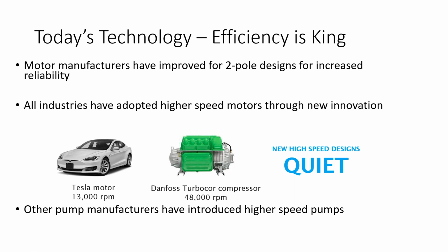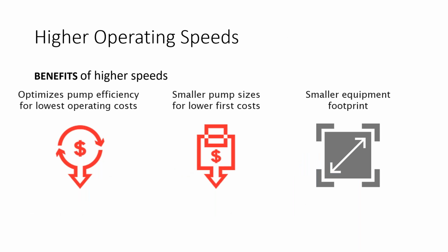Efficiency is king, right? Motor manufacturers have improved the 2-pole designs for increased reliability. All our industries have adopted higher speed motors through innovation. Tesla, for example, runs its motors at 13,000 RPM, and I'm sure you'd agree that Tesla snuck up on you every once in a while, and you're shocked to see it there because you didn't even hear it. You might have heard a little tire noise. That's about it. Those motors are extremely quiet. Danfoss has a turbo core compressor that runs at 48,000 RPM. And of course, other pump manufacturers have introduced higher speed, but the new high speed designs are very quiet. The benefits are we're going to increase the pump efficiency for lowest operation costs, and lower the footprint because a smaller motor is smaller, of course.